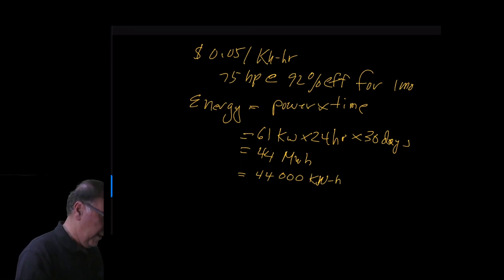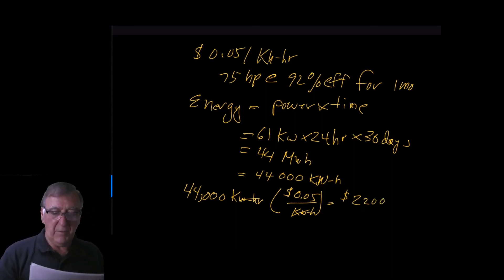And looking at the cost, we would say that we have 44 thousand kilowatt hours times the rate cost 5 cents per kilowatt hour. Again using our dimensional analysis here, this goes out, this goes out, and that equals $2200. So every month it would cost you $2200 to run a 75 horsepower motor 24/7.